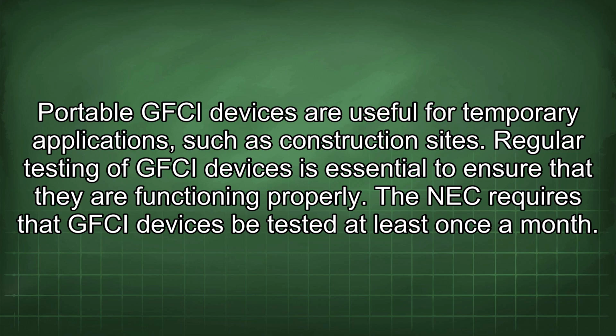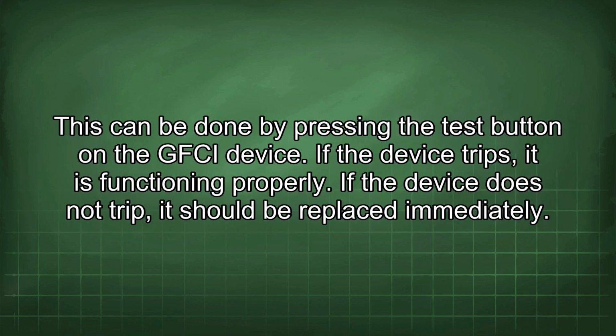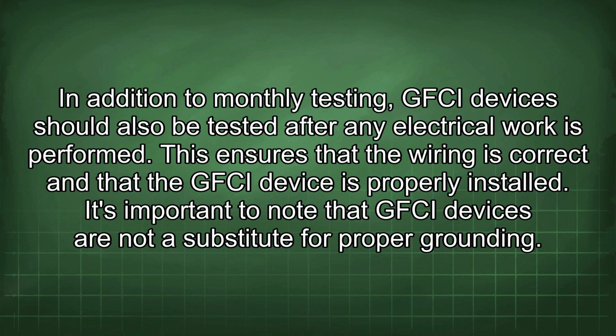Regular testing of GFCI devices is essential to ensure that they are functioning properly. The NEC requires that GFCI devices be tested at least once a month. This can be done by pressing the test button on the GFCI device. If the device trips, it is functioning properly. If the device does not trip, it should be replaced immediately. In addition to monthly testing, GFCI devices should also be tested after any electrical work is performed. This ensures that the wiring is correct and that the GFCI device is properly installed.